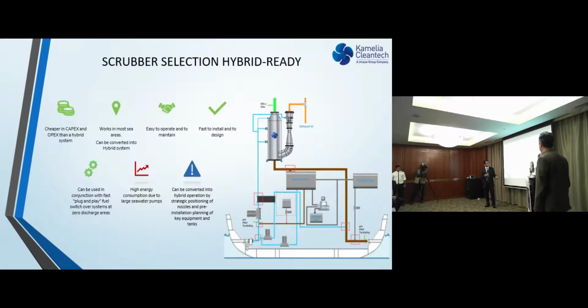We treat it with alkali, and in closed loop, the pH out of the scrubber never actually goes below 5.8 or so, so you don't really need to treat it further. The pH is higher because you're treating it with a very strong base, the alkali, caustic soda. That's the chemical dosing, raising the pH very fast.